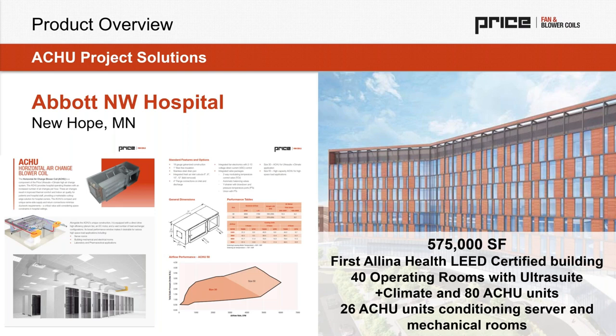And they wanted that for a few reasons. The first was that with additional airflow, load could be managed with an elevated supply air temperature. We found and heard from surgeons and nurses and surgery support staff that in order to make the room a comfortable temperature below the laminar flow diffusers, they were finding that the supply air was too cold. And even though it was laminar flow, it was almost verging on feeling a little drafty. And that's not ideal, especially if you imagine, I don't want my surgeon to be too cold.